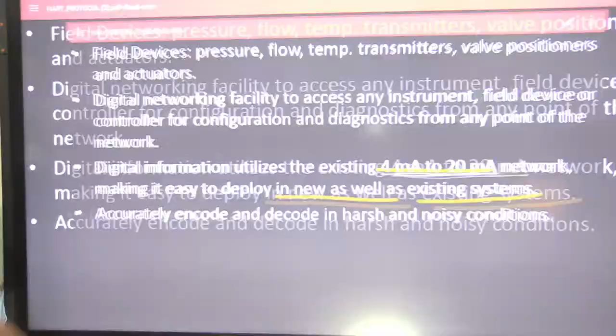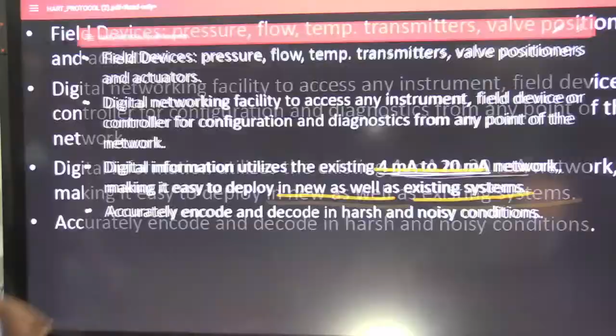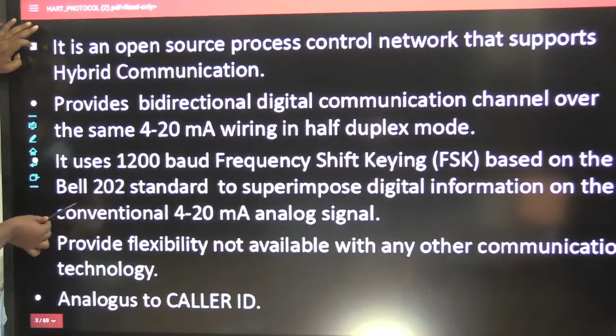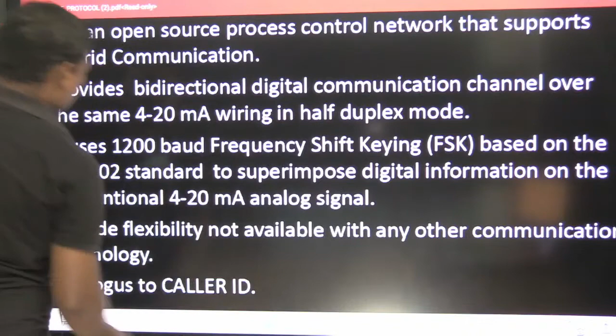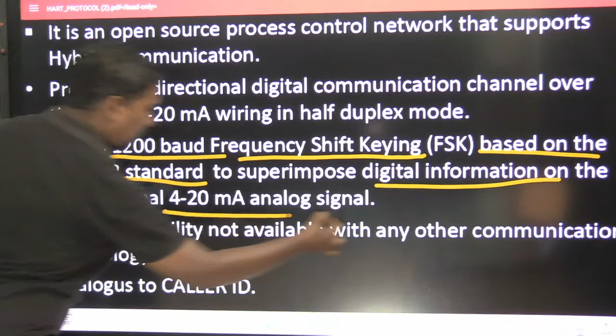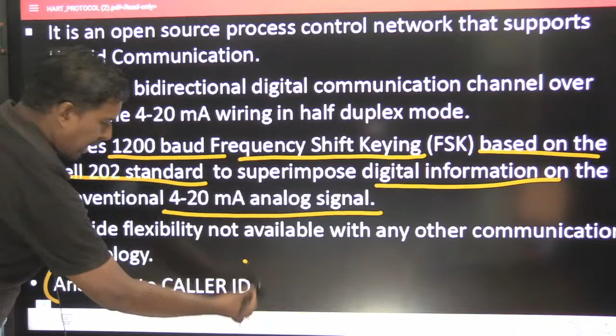As I told you, what is the history of this? Just before, I told you the caller ID is a history. Generally it uses 1200 baud frequency, please make a note of it. It uses 1200 baud frequency shift keying based upon the Bell 202 standard to superimpose digital information on the 4 to 20 milliamperes analog signal. It is just analogous to caller ID.